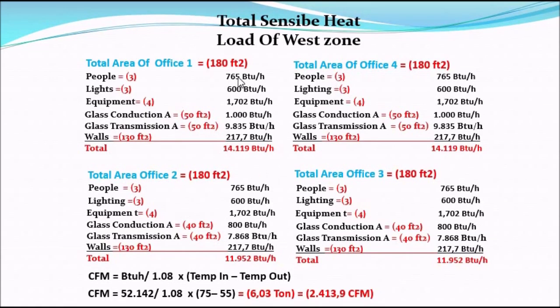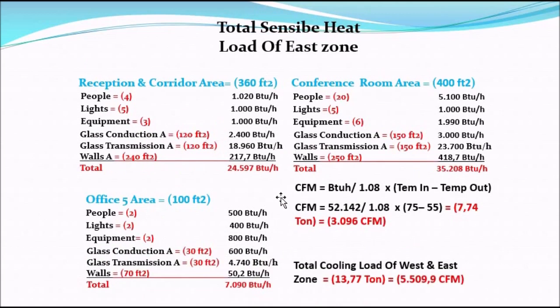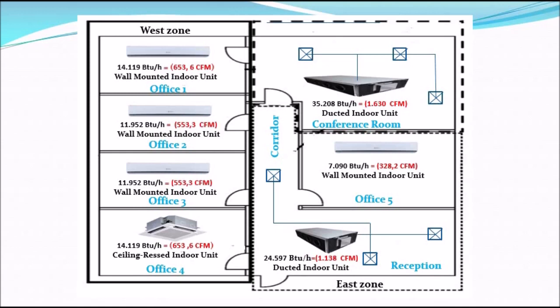I have already calculated the loads for each zone. To determine the required CFM, use the formula: CFM = BTU/hr ÷ (1.08 × (T_return − T_supply)). Adding all numbers together gives a total of 13.77 tons, equivalent to 5509.9 CFM. I've also included an example showing how to select the air handler unit for each space. That's it for today — thank you for watching.